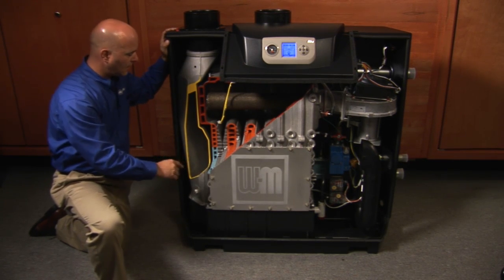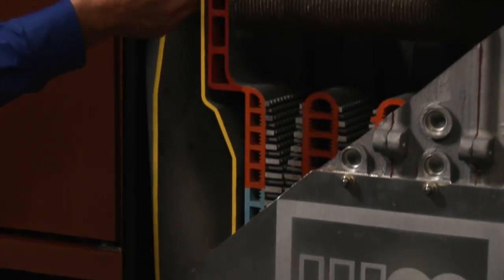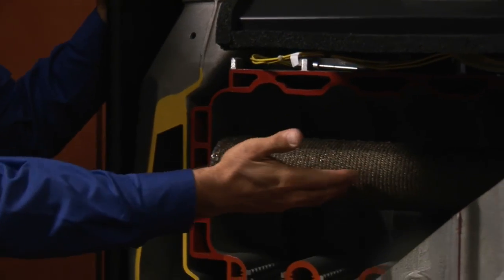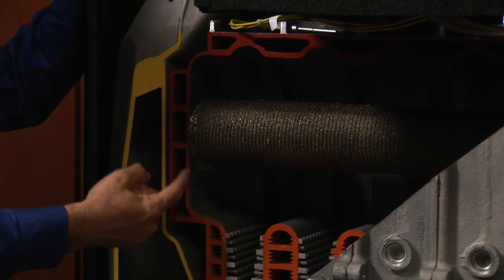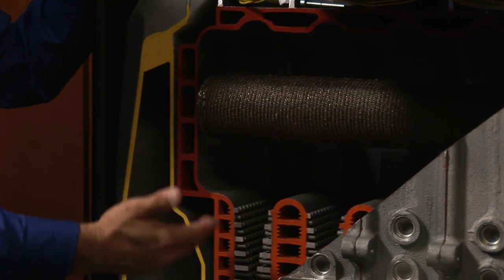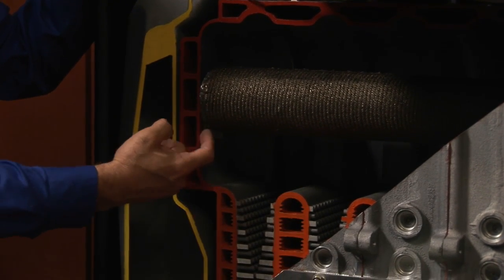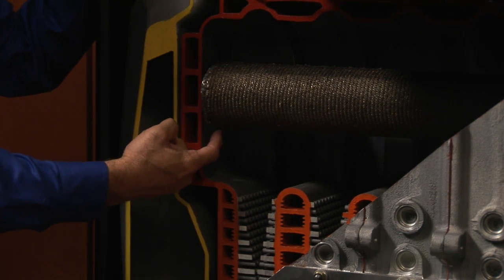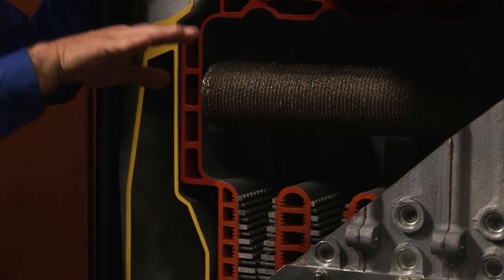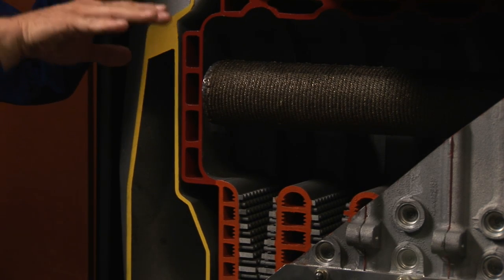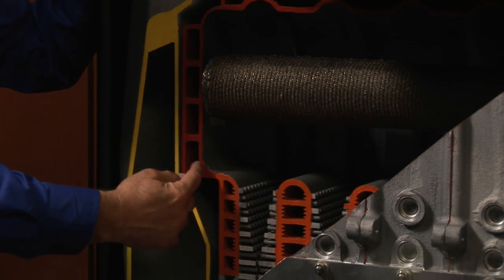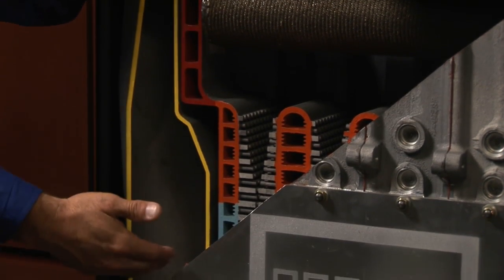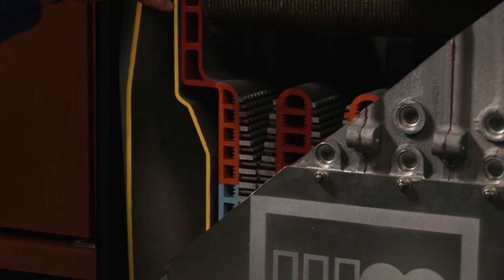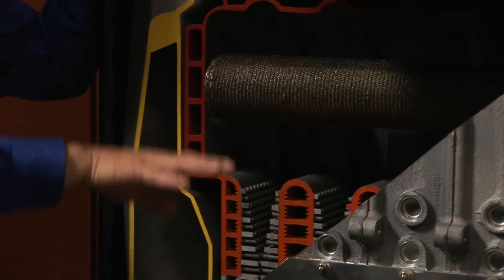This is a cutaway boiler, and what we have here, this is the burner, and on the rear section, this is a 750,000 BTU heat exchanger. On the rear section, there's tabs that the burner sets in to make sure that the burner mounts into the boiler level. These are the waterways. The water pattern on this boiler is from the bottom up. The flue pattern on the boiler is from the top down.